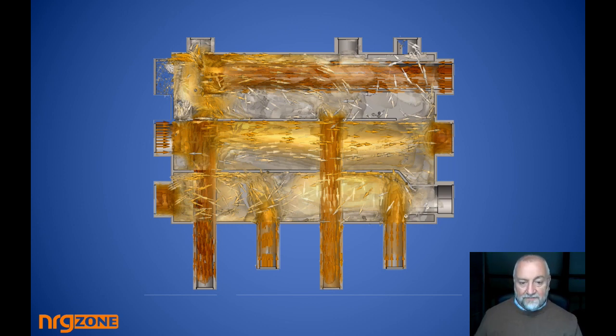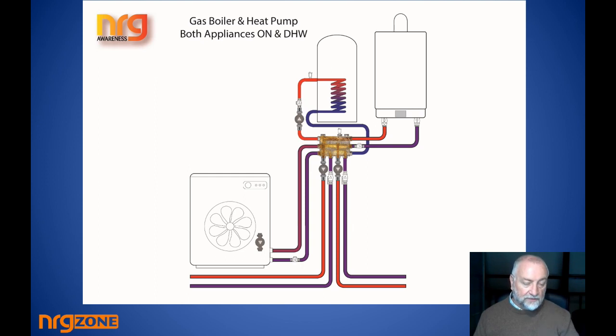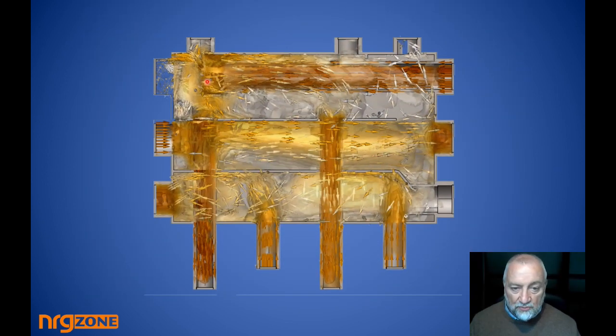We're going to go one step further, and we're going to add a little dimension that's very unusual but very useful. Before we decide to head across to feed our zones, we want to put on a hot water zone taking the highest temperature water. Because the hot water is coming in from the gas boiler here, when it's collected at this point, it can be taken by the gas boiler flow up to the coil of the cylinder, heats the cylinder, and the return comes back into the unit from the cylinder, and therefore it allows the cylinder to operate at high temperature, whereas the heat pump is still delivering in here, and depending on how much water the system is taking away, you could allow for enough for some of the water to be taken back up here from the heat pump alone. But it comes down to your calculations, your pipe sizing and your pump sizing. But again, you can have an additional high temperature cylinder up here, even though you're feeding it through preheating from the heat pump.